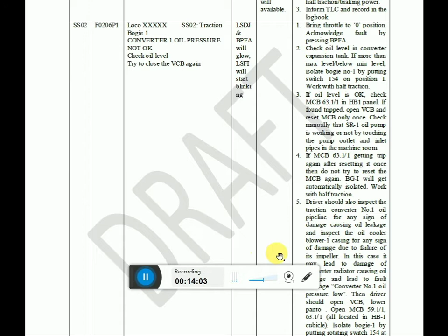Similarly, F0206 P1, converter 1 oil pressure not okay. So we have to ensure MCB 63.1/1, converter oil pump MCB working or not. If any MCB trips, we can reset. So if this message is there, we have to check first the oil level in the traction converter. If oil level is okay, it should be above the minimum mark.